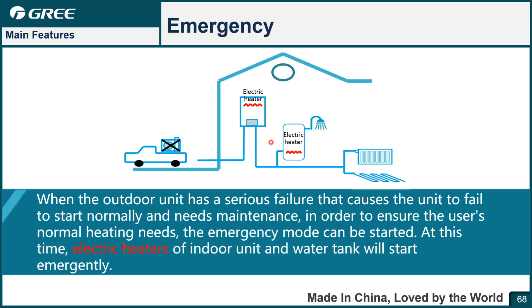Emergency function. In case of outdoor unit malfunction, maybe you need to repair, and then you can set the emergency running. In this case, the unit will use the e-heater in the hydro box and the e-heater in the water tank as a backup for heating, so that the whole system can still run, and then you can get some emergency troubleshooting time to repair the outdoor unit.